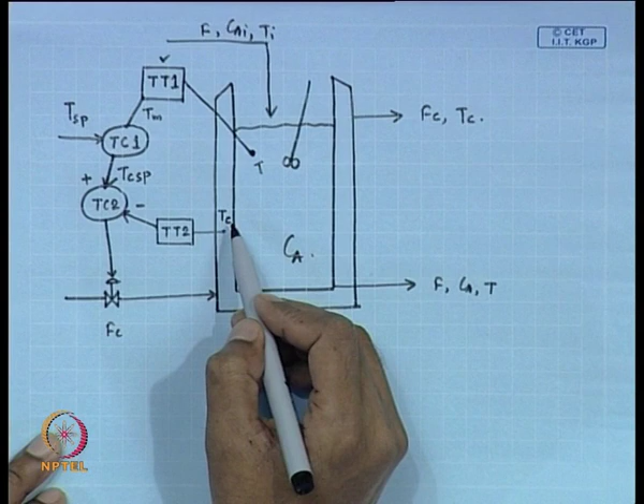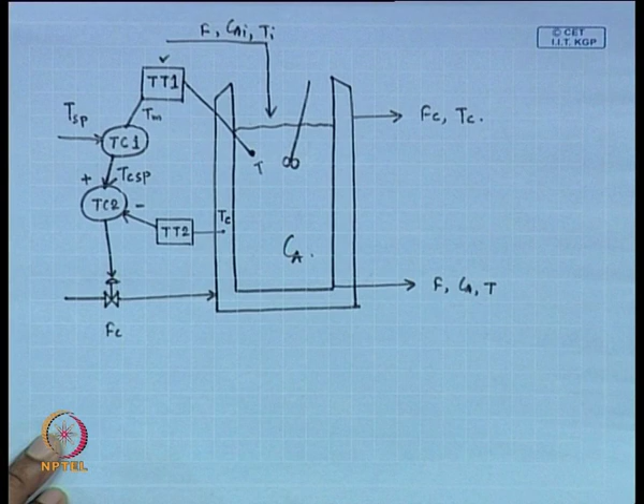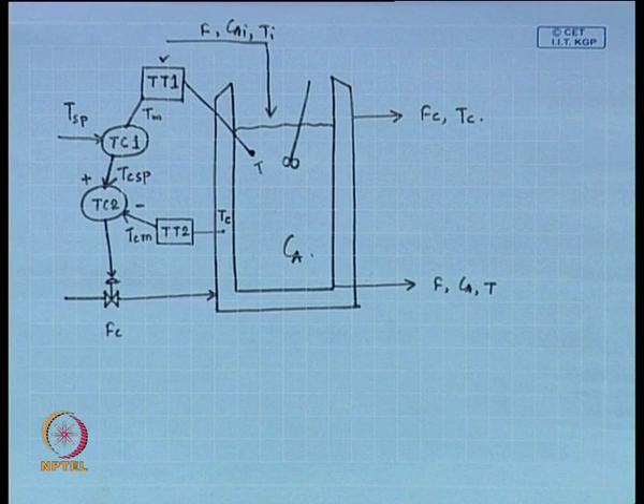The second measuring device TT2 basically measures Tc, which is the disturbance involved with the manipulated variable. So, this signal is basically Tcm, measured Tc. So, Tc set point is compared with Tcm, and the second controller TC2 calculates the control action, and that action is implemented through this control valve. Fine. So, here TC1 is the primary controller or master controller, and TC2 is the secondary controller or slave controller.